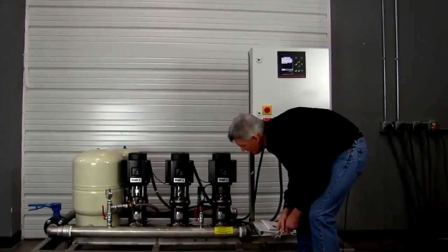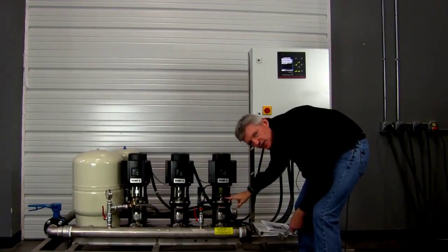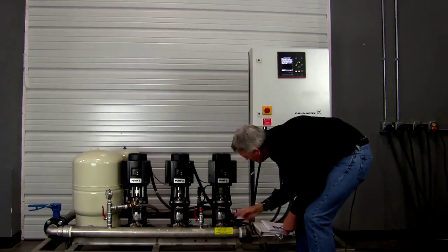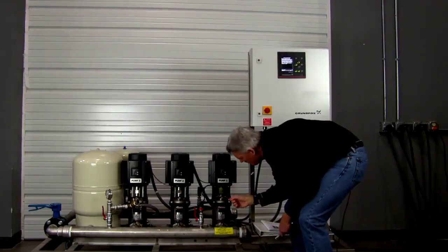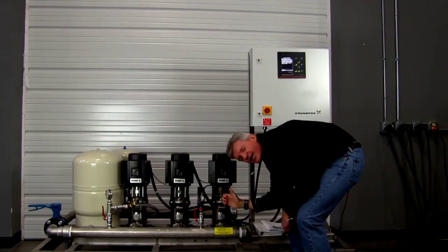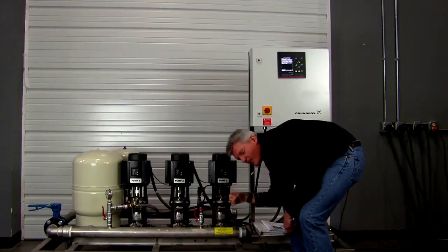For rotation check, we're going to stop the pump, and then we're going to view the rotation of that coupling there. So when it comes to a stop, we want it to be working in the counterclockwise direction, looking down. So I use the right hand rule. It's got to go in the direction of my fingers. As you can see, it was going in the correct rotation.